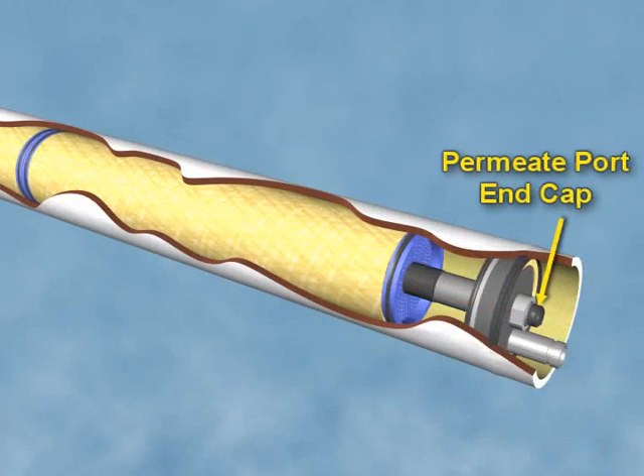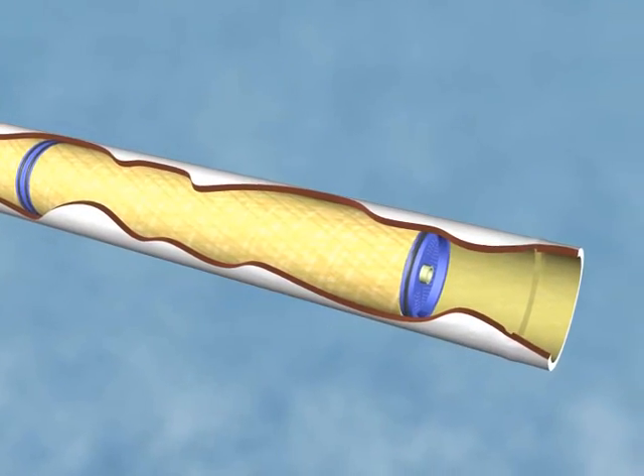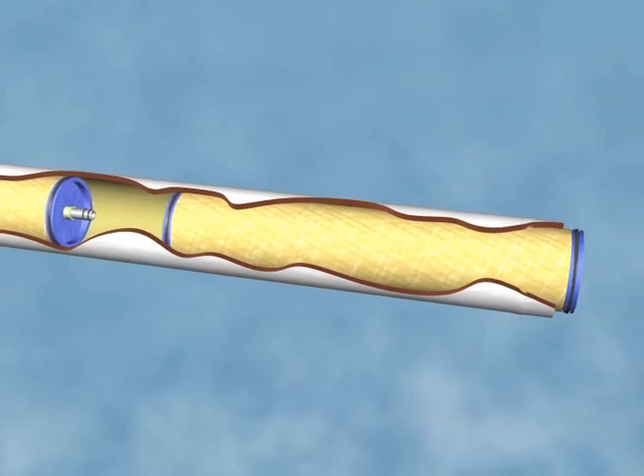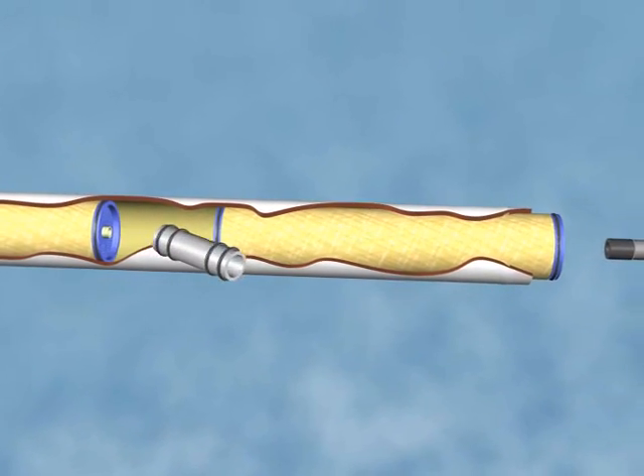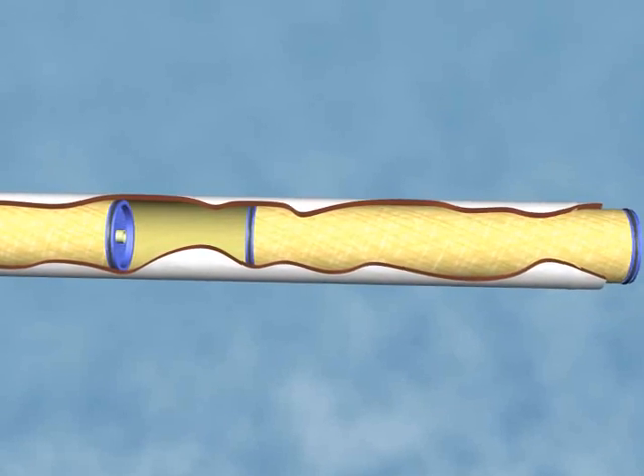Typically, one end of the pressure vessel's product tube is capped while the other is open to allow product water to exit. The couplers generally have double O-rings on each side. These O-rings on the couplers are used to prevent higher pressure feed water from passing into the product tube, thus contaminating the product water.